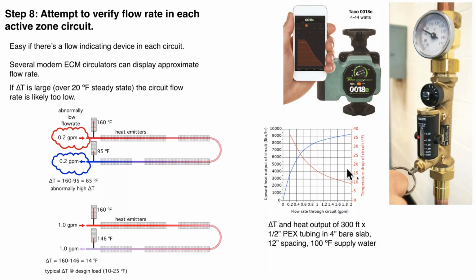water. And I just want to show you the temperature drop of the circuit can vary a lot. If we're doing 2 gallons per minute into that circuit, we're actually a little under a delta T of 10. And then as we decrease flow, you can see the delta T keeps going up. If we got way down here to 0.2, we'd have a delta T of like 35, but maybe 37 degrees Fahrenheit. Again, if you're taking temperature measurements on a floor circuit or even a baseboard circuit, and you're seeing 35 plus degree delta T's, it's almost always indicating insufficient flow. And now it's up to you to go find what is the cause of that insufficient flow.